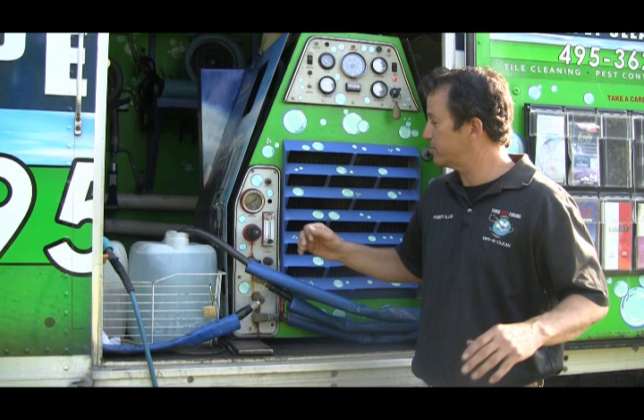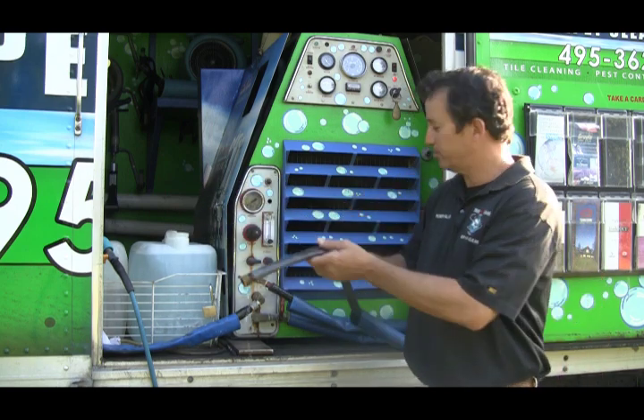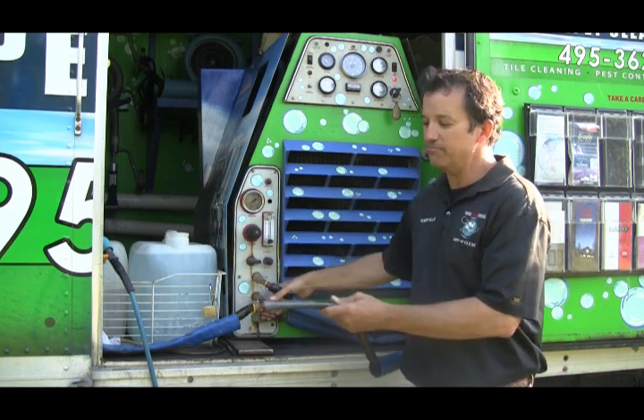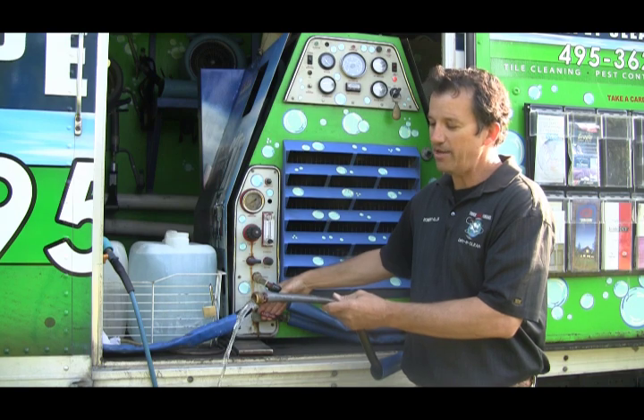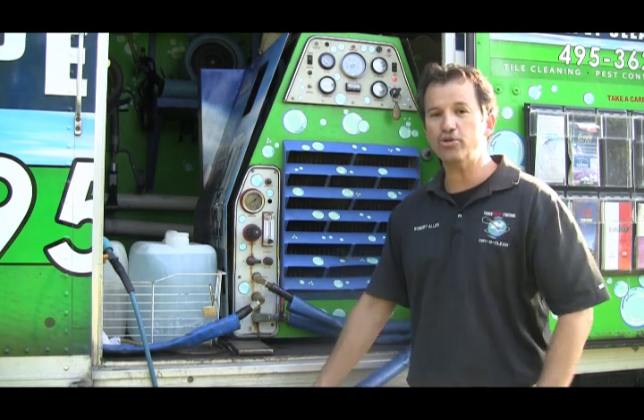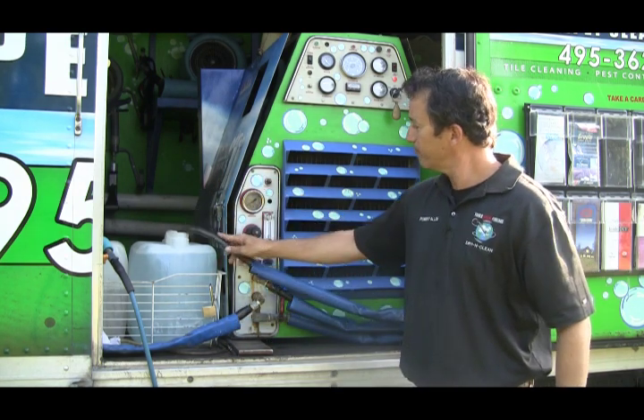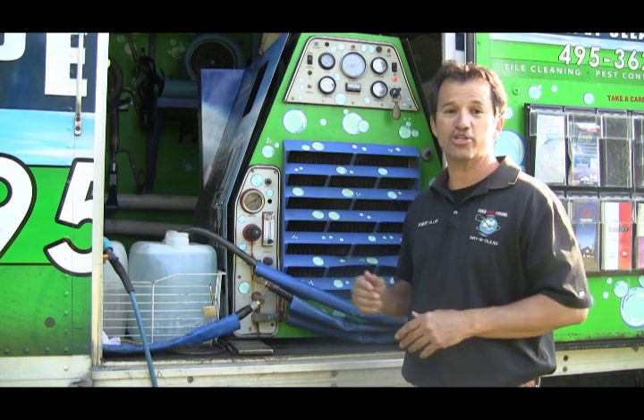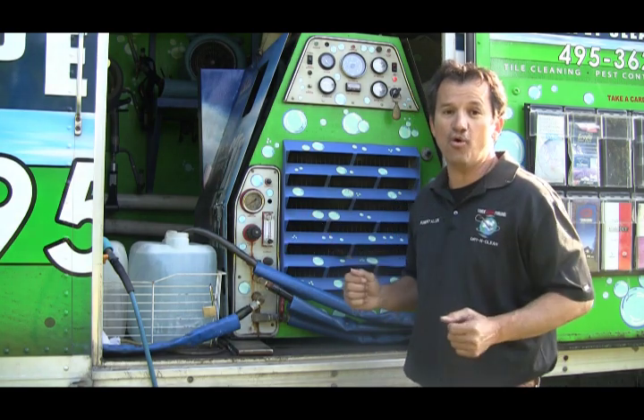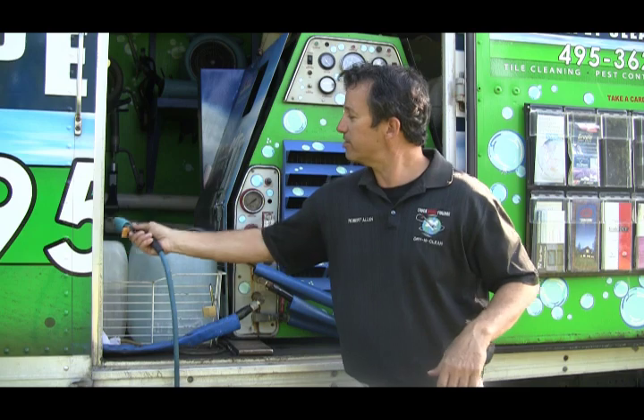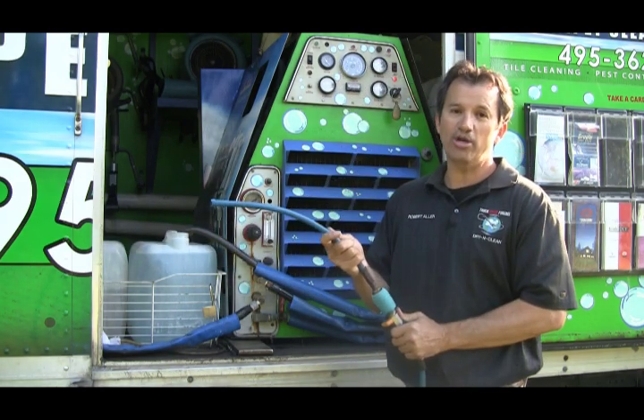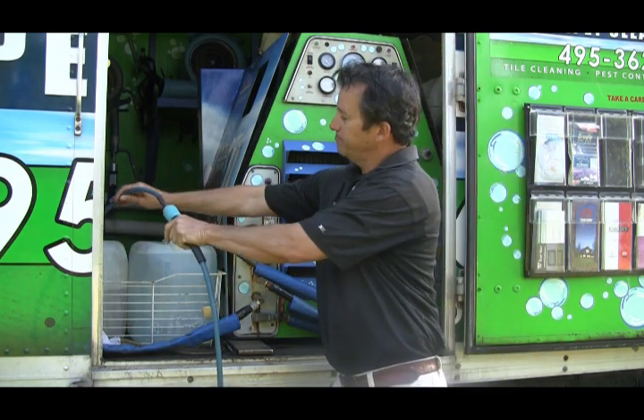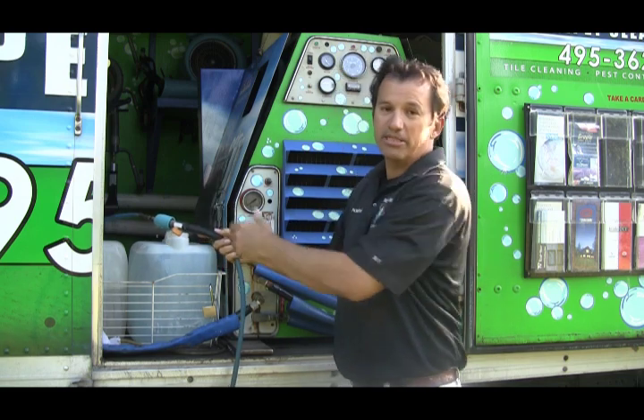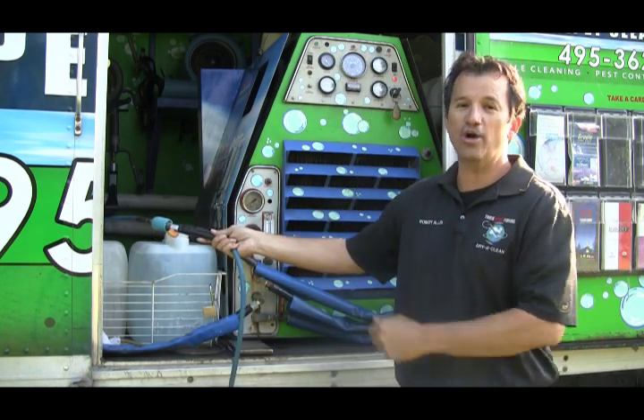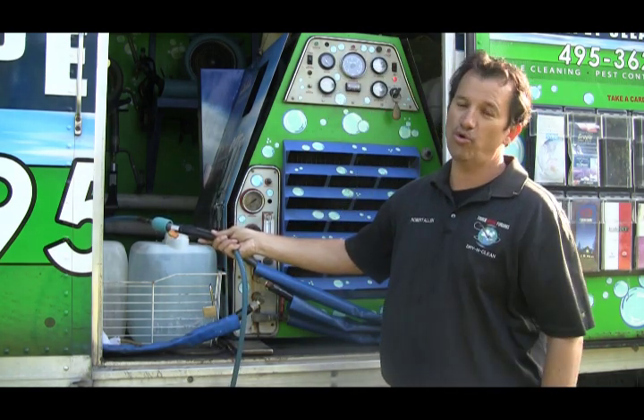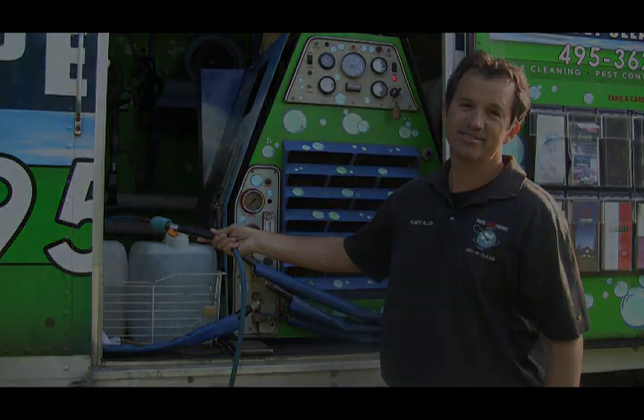Some of these come with a bleeder valve, some come with a bleeder hose. This one comes with a bleeder hose, and you can bleed the water right out, no problem. The one issue is that it only bleeds to one heat exchanger, not all 4 on this unit. So I hook up my drain hose again, put it in my 5-gallon mix tank on the other side, and drain it. This takes care of cooling this unit down properly.